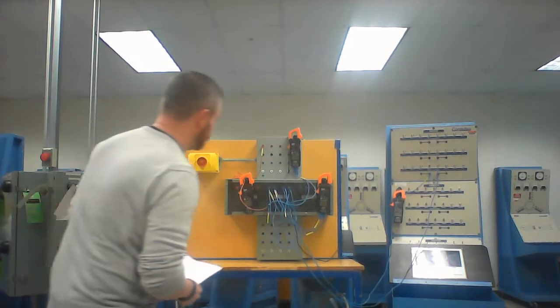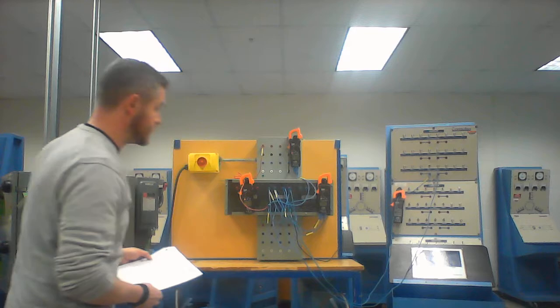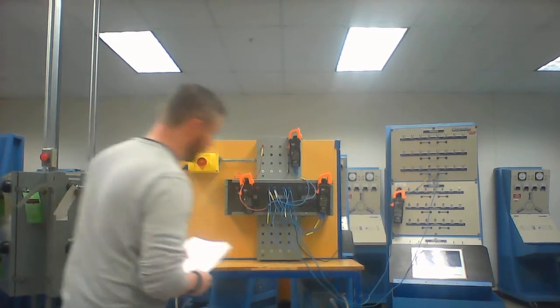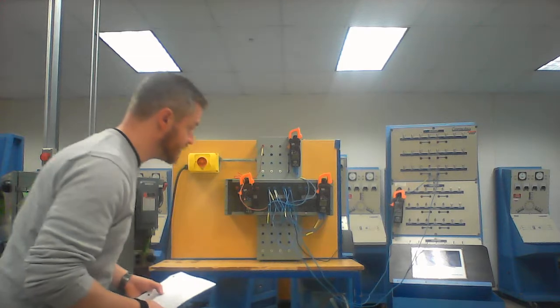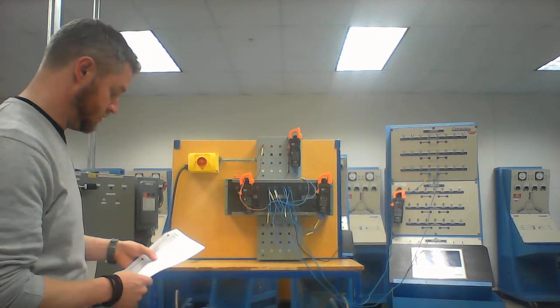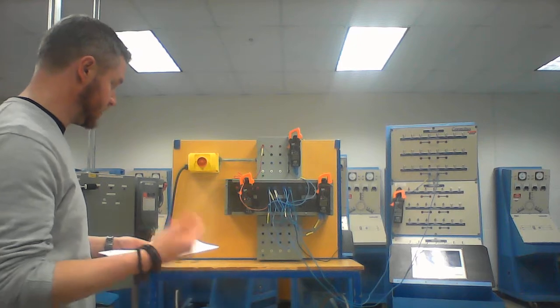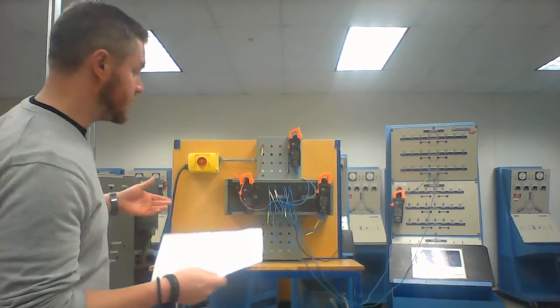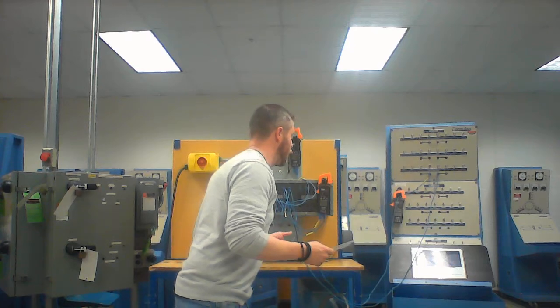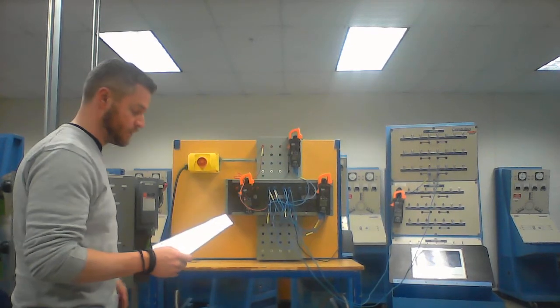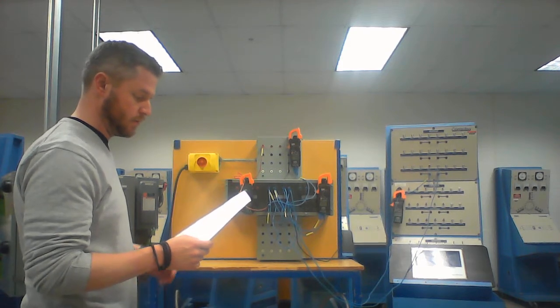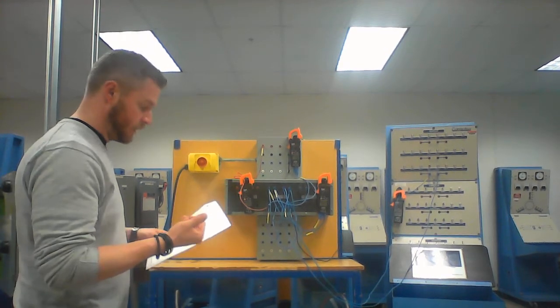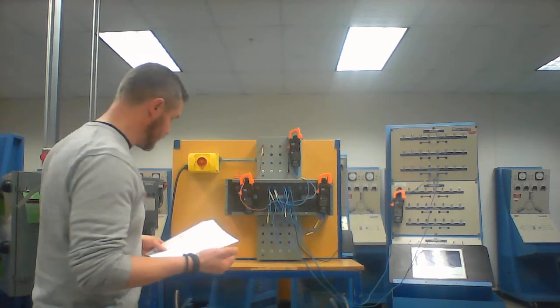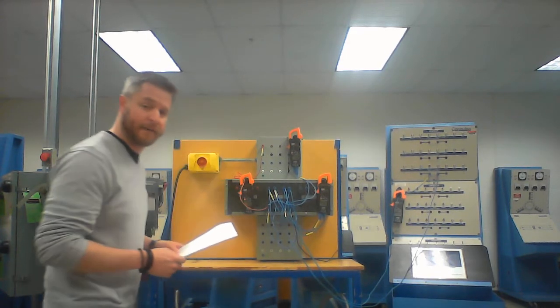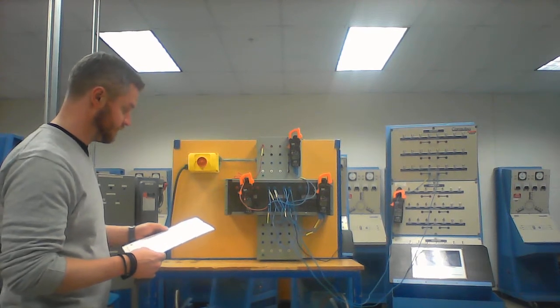Okay. Primary voltage, 117. Secondary voltage, 186.7. Voltage ratios we'll do later. Excitation current was the same. Measured secondary current, 0.39 amps with a 440 ohm resistor on. Okay. Calculating my primary current, 0.78, and I'm reading 0.75. Okay. Well, that's good. That's with 440 ohms.